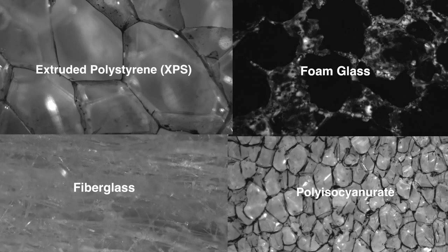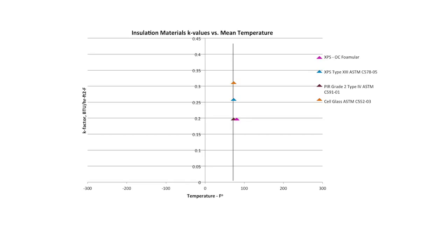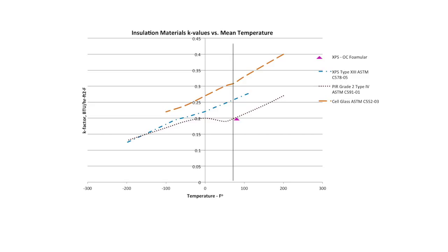Why is this distinction relevant when evaluating thermal conductivity? Insulation materials with trapped gases or blowing agents have a unique characteristic that must be considered: the boiling point of the gas itself. As illustrated on this chart, the thermal conductivity of the insulation changes as the temperature approaches the boiling point of the trapped gas. This results in thermal conductivity values that are not consistent through the range of temperatures to which the insulation will be exposed.